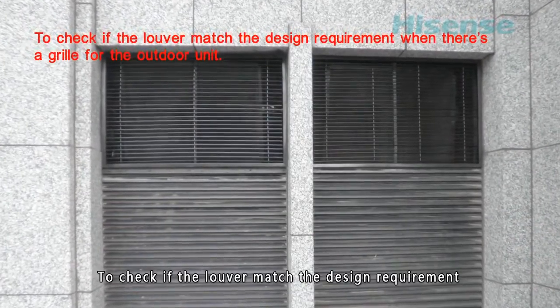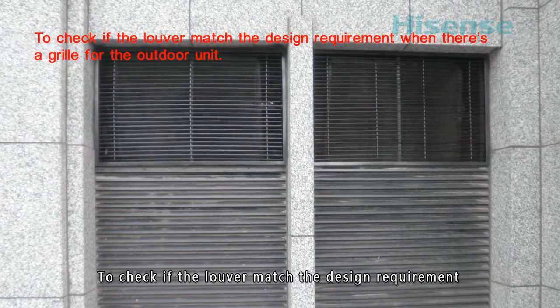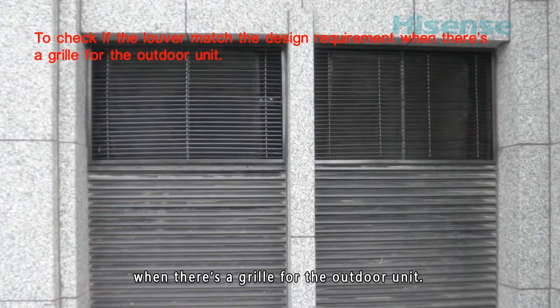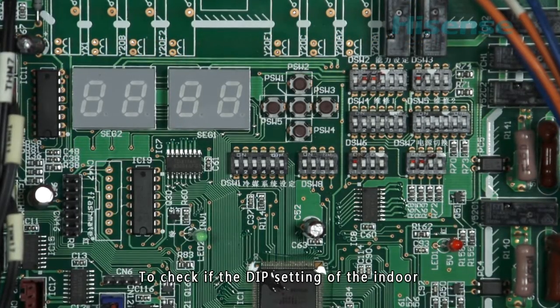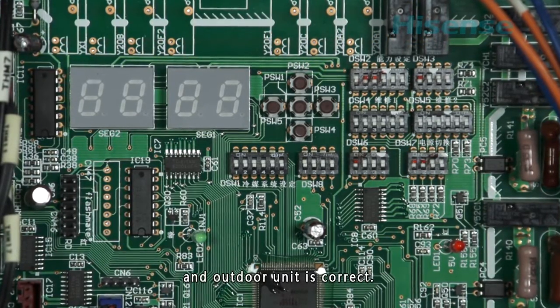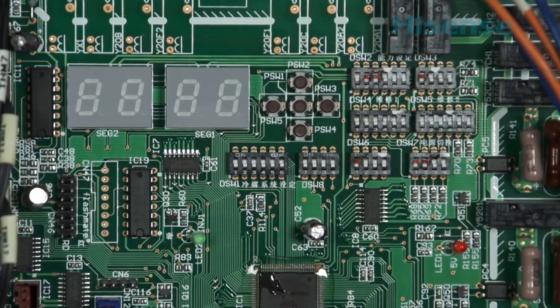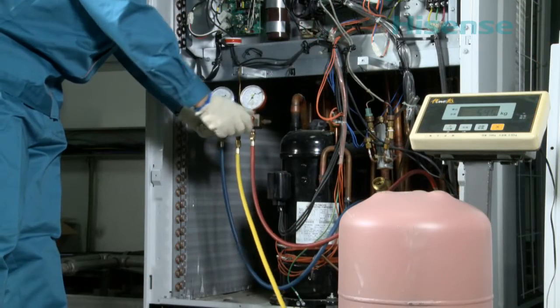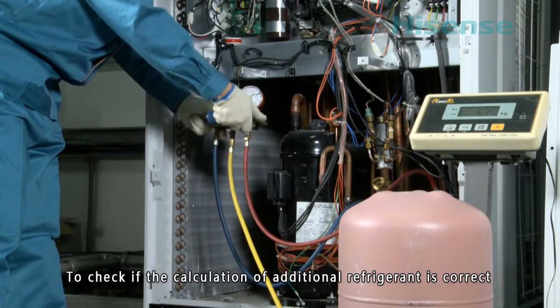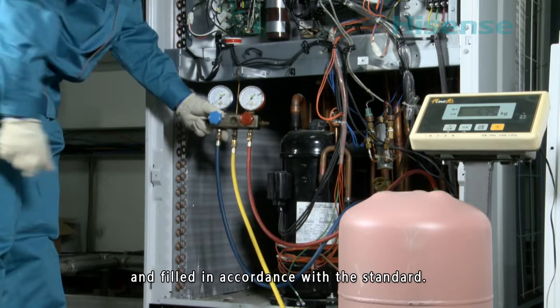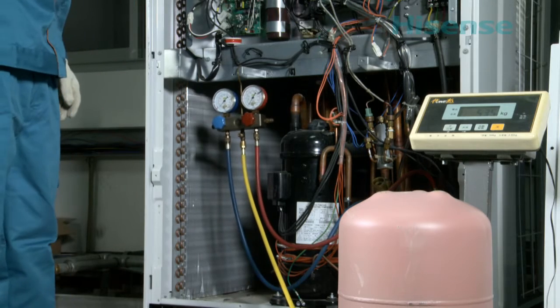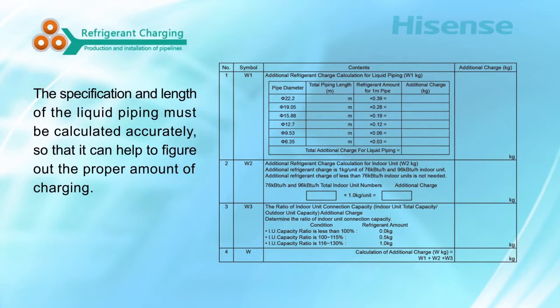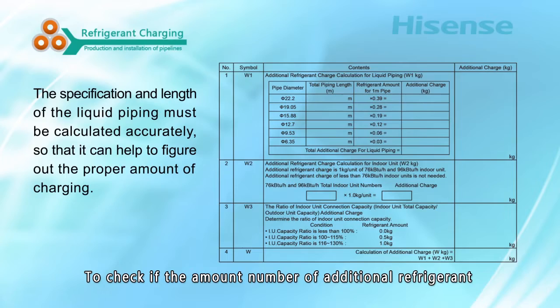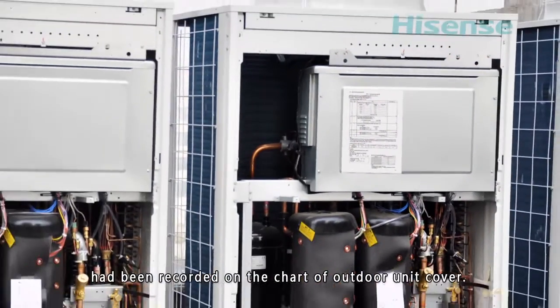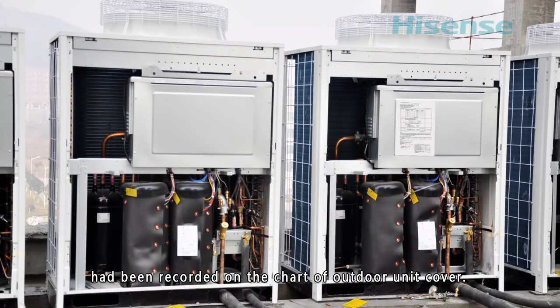5. To check if the louver matched the design requirement when there's a grill for the outdoor unit. 6. To check if the dip setting of the indoor and outdoor unit is correct. 7. To check if the calculation of additional refrigerant is correct and filled in accordance with the standard. 8. To check if the amount number of additional refrigerant has been recorded on the chart of outdoor unit cover.